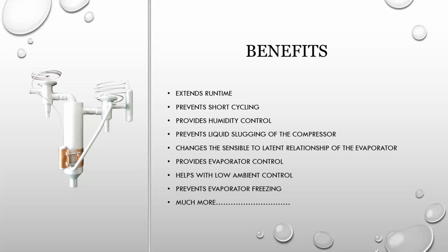Changes the sensible to latent relationship of the evaporator. That is in percentage terms. There is only so much latent removal an evaporator can do, but what this does is when it unloads and there's a presence of high humidity, this causes it to unload sensible rather than latent energy.